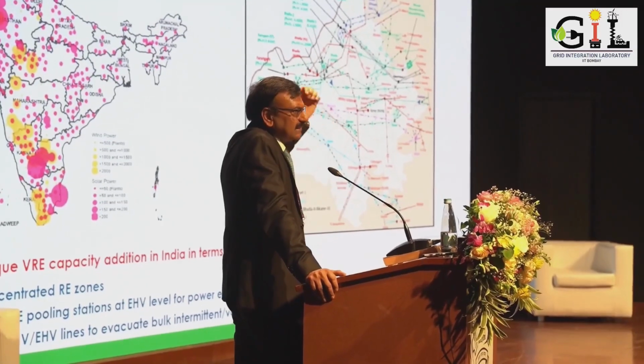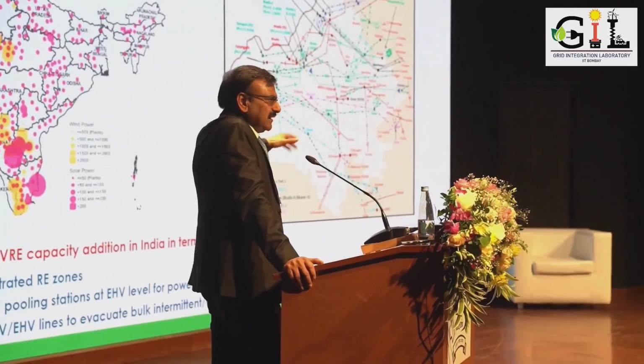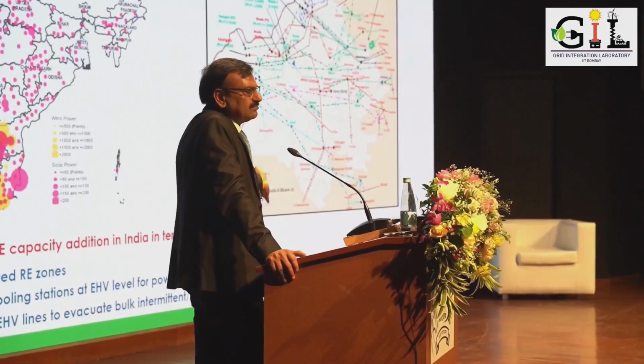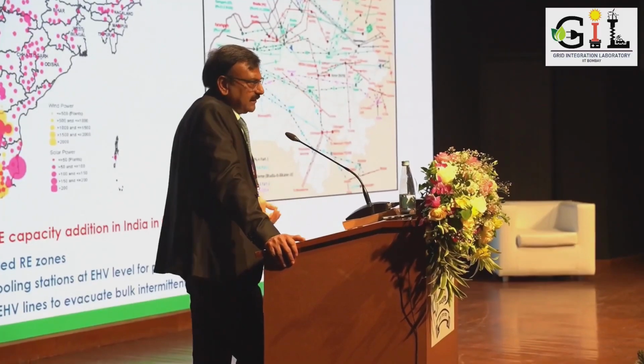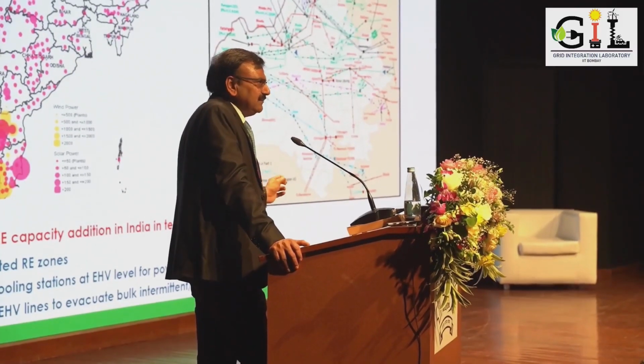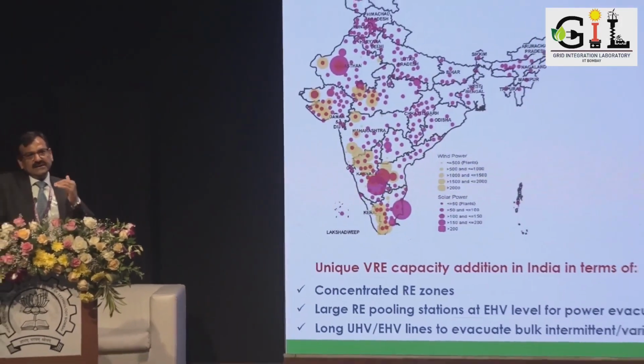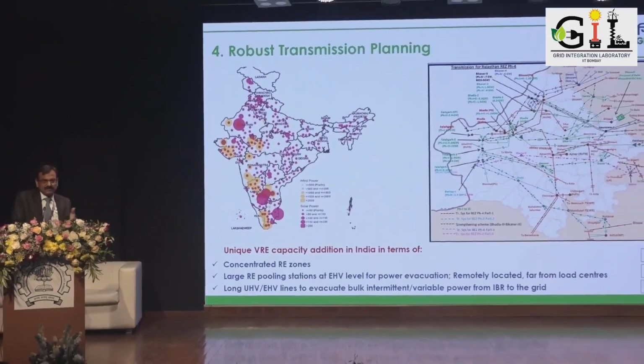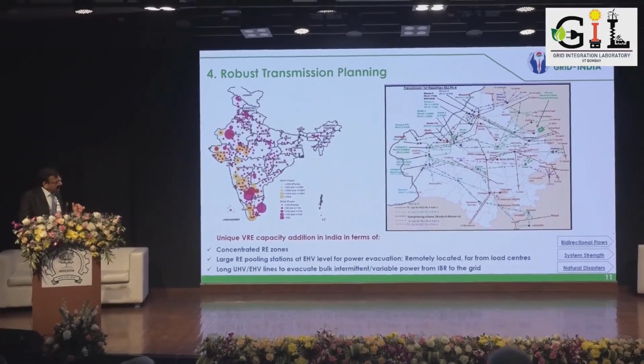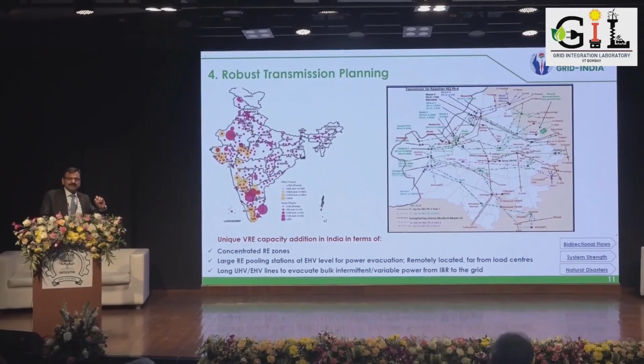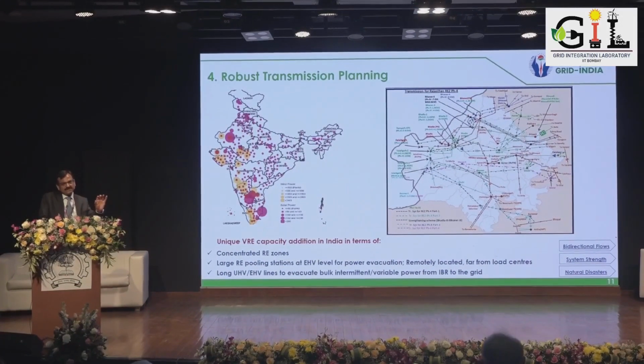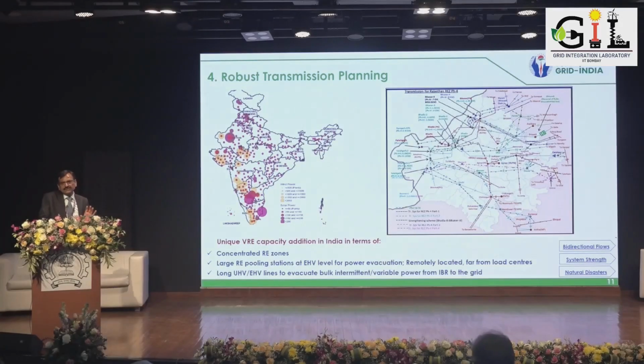The problem is that as more and more high voltage lines come up, presently we have to switch on and switch off 30-40 lines daily in that particular area. Any miscalculation or delay anywhere can create a problem, because that will hinder the solar ramping up on its own pace. And if there is any delay in synchronizing any line, we are in trouble because some other section will get overloaded. So all this has to be done very meticulously, in a very fast, very small time window.